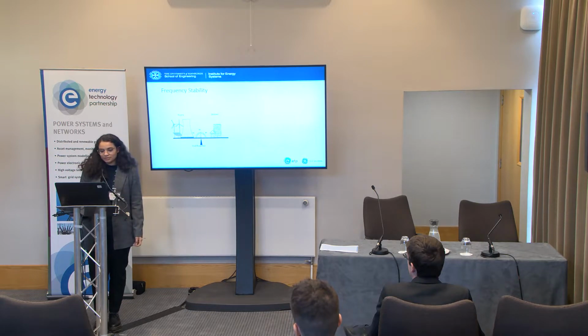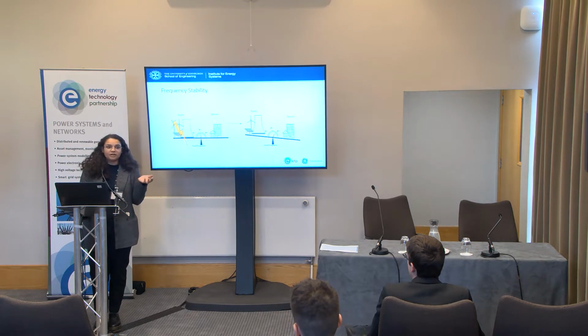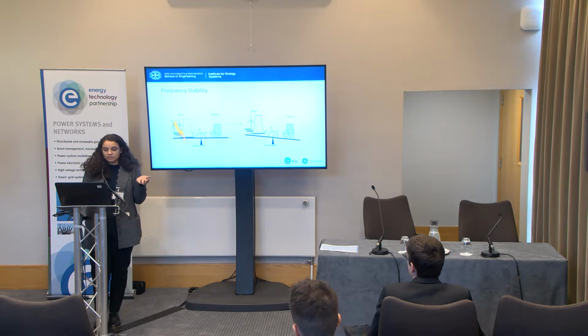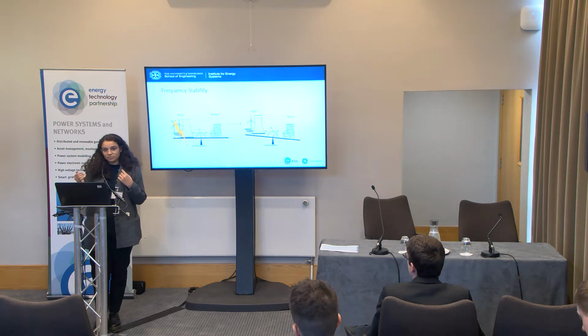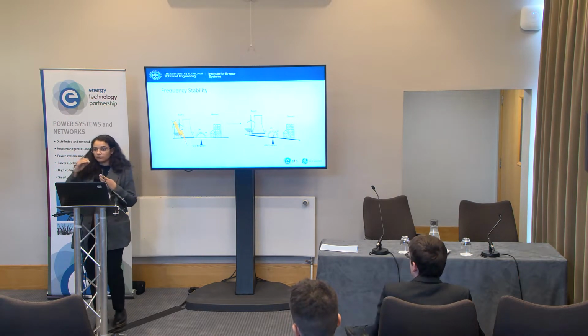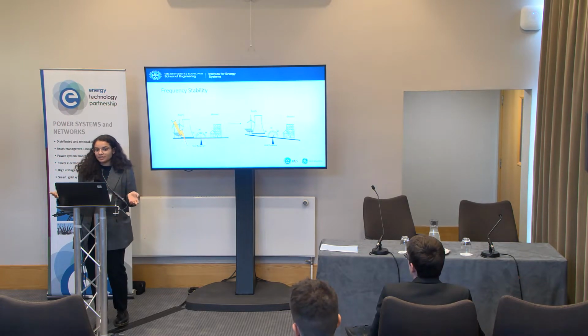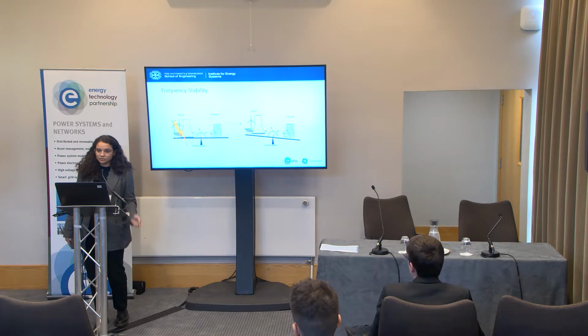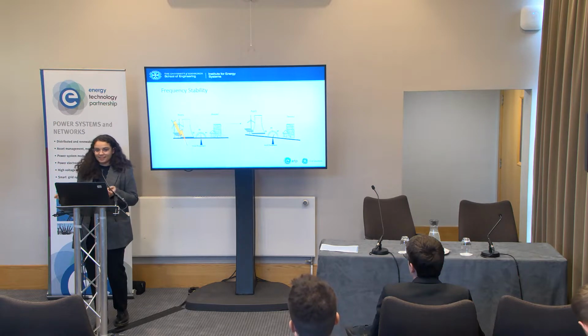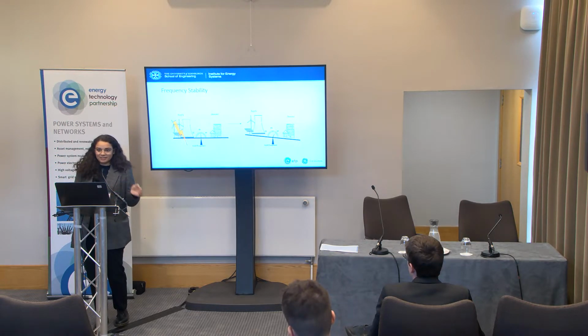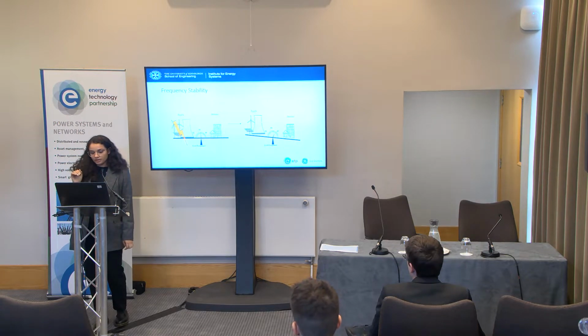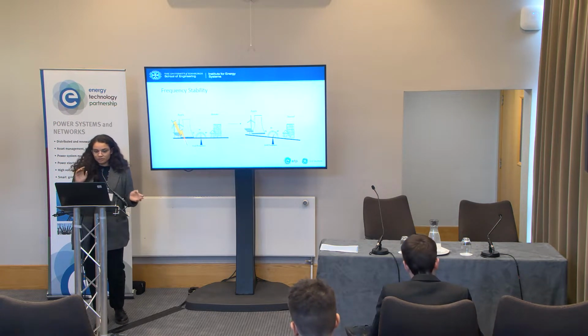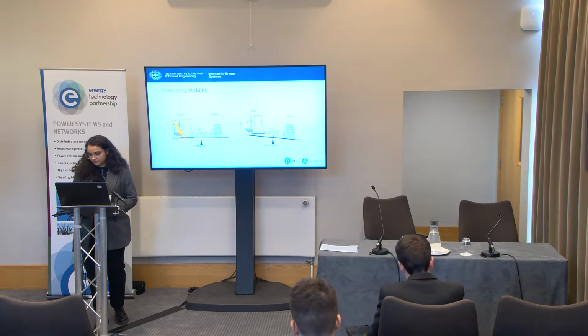However, sometimes there's a fault, like a lightning strike, and that causes the balance to change faster, because that will increase the frequency, or it will make an overcurrent, which means that protection devices will disconnect things. It will disconnect generators, it will disconnect loads. When that happens, the frequency changes more, and then something else disconnects, and it can cascade, and that will cause a blackout. The energy system operator will work to stop that from happening.